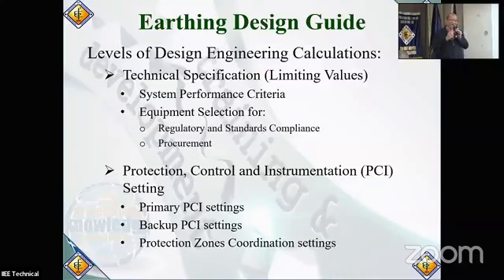Dahil kung nasa generation side ka, more likely than not, that generation capacity is less than the grid capacity. So what is the fault duty that prevails into your system if your high voltage system is connected to the grid through the grid connection facility? My advice is hanapin mo muna yung grid fault duties na nandun. Because kahit generation ka, magkaroon ka ng fault sa generation side or dun sa primary side, it's still the fault duty of the grid that will dictate the whole system.